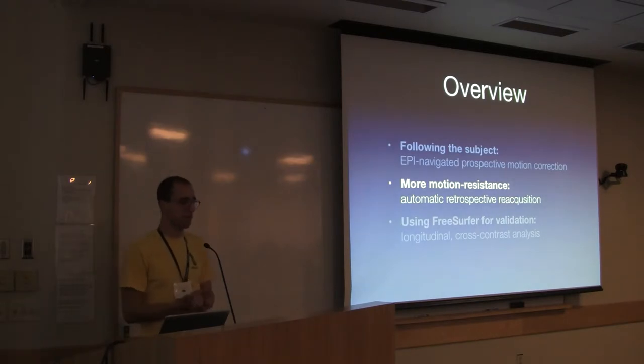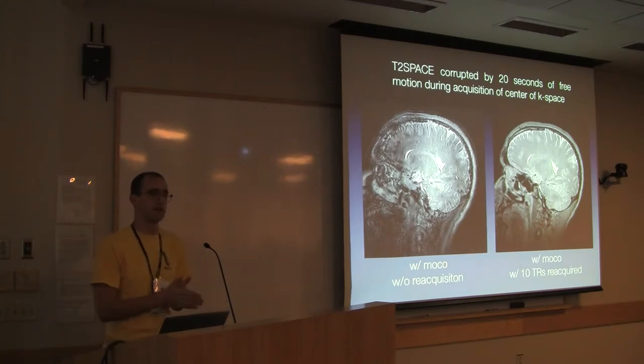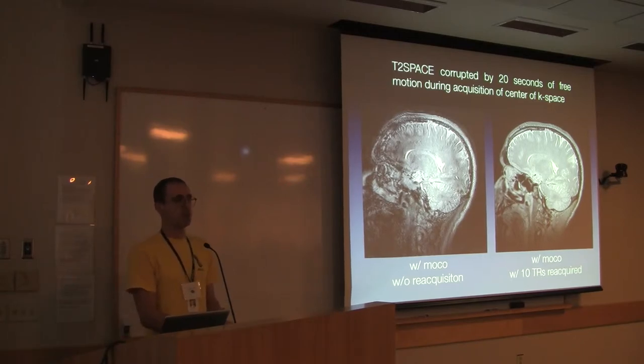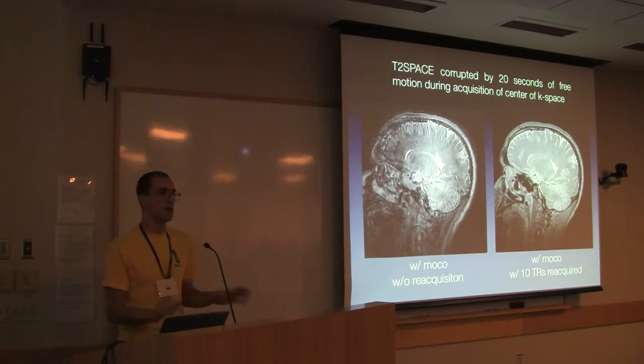Now we're going to talk about the second part of this system which does automatic reacquisition. This is the slide where you're all going to suddenly think that I've been lying to you about the fact that this works. This is a T2 space scan where the subject thrashed for the central 20 seconds of the scan. Again, not huge motions but continuous motion for 20 seconds. If we just did our motion correction then we get the image on the left which isn't awesome. If we do our motion correction and we tell the sequence to automatically reacquire the parts of the scan that were motion damaged then we get the image on the right. That's obviously a lot better. I'm going to talk about why we do reacquisition as well, why motion tracking just isn't enough.